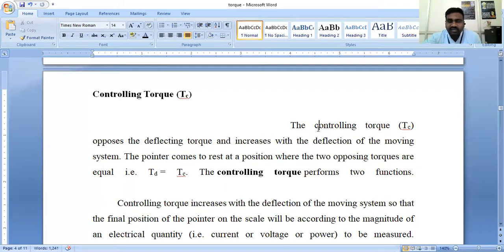If you see in some of the damaged meters, if we connected them in the lab, in some meters the needles start oscillating from 0 ampere to the maximum range. That means from 0 amperes to 2 amperes, 2 amperes to 0 amperes, they go on oscillating and deflecting without any control.